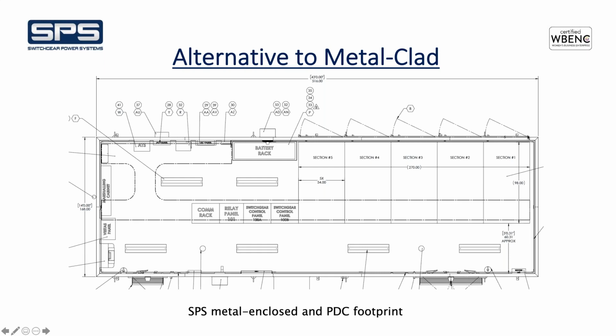One advantage of doing the PDC construction was they also incorporated the relay panels for the entire substation in our PDC, and we built those. They have their batteries and a panel for the turbines. So it turned out to be a very nice design, and we actually were able to offer our customer about a 12% savings overall on the entire switchgear PDC package compared to the metal clad option. So that was just their upfront cost to us. And then it would have saved them any amount of time that they would have spent at site reconnecting the PDC and reconnecting any wiring that had to be unterminated for shipment.